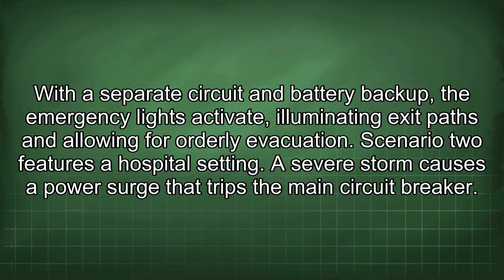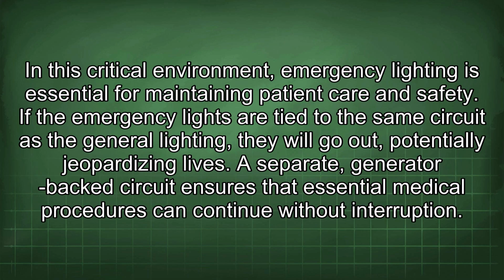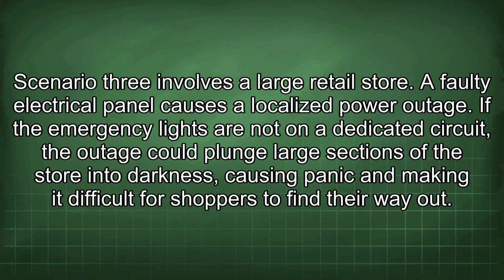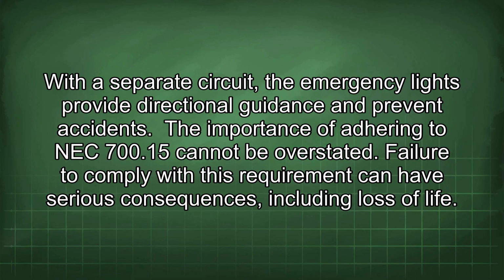Scenario 2 features a hospital setting. A severe storm causes a power surge that trips the main circuit breaker. In this critical environment, emergency lighting is essential for maintaining patient care and safety. If the emergency lights are tied to the same circuit as the general lighting, they will go out, potentially jeopardizing lives. A separate generator-backed circuit ensures that essential medical procedures can continue without interruption. Scenario 3 involves a large retail store. A faulty electrical panel causes a localized power outage. If the emergency lights are not on a dedicated circuit, the outage could plunge large sections of the store into darkness, causing panic and making it difficult for shoppers to find their way out. With a separate circuit, the emergency lights provide directional guidance and prevent accidents.